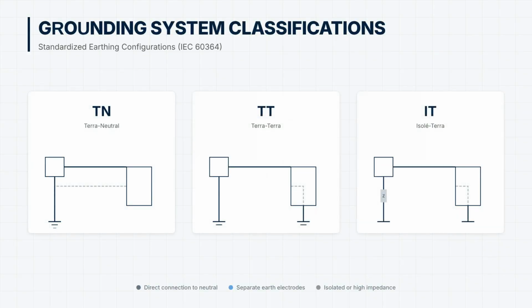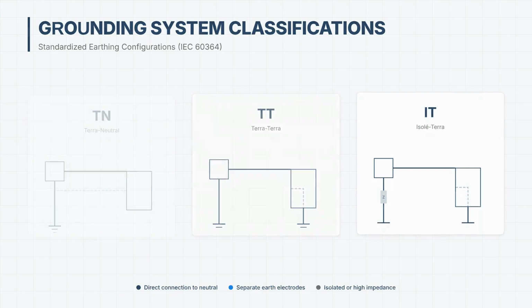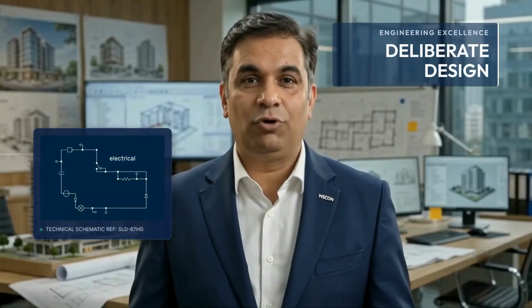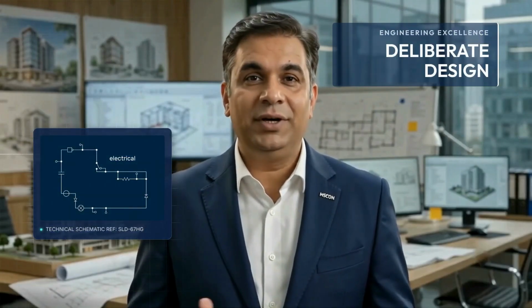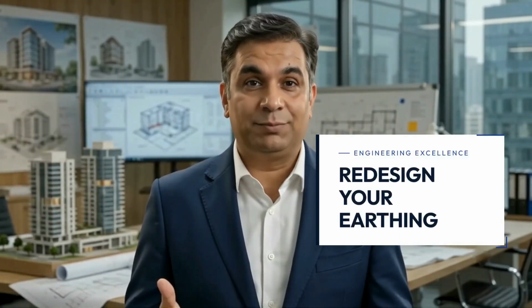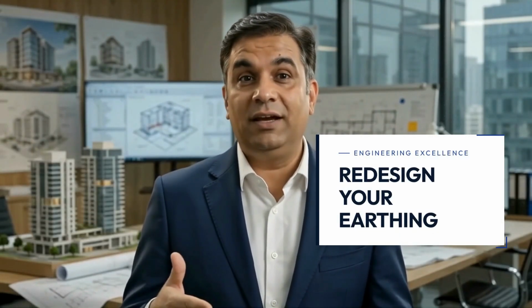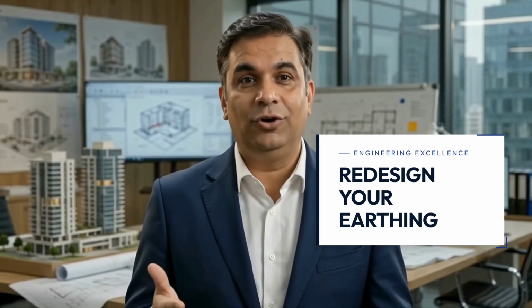TN, TT, and IT systems and their subclassifications. It emphasizes protective equipotential bonding, tying metal parts together so there's no dangerous voltage difference. And earth fault protection is treated properly. So earthing is now a deliberate design choice for the building, not a standard drawing you copy from the last project. If you design one thing carefully after this video, make it your earthing.